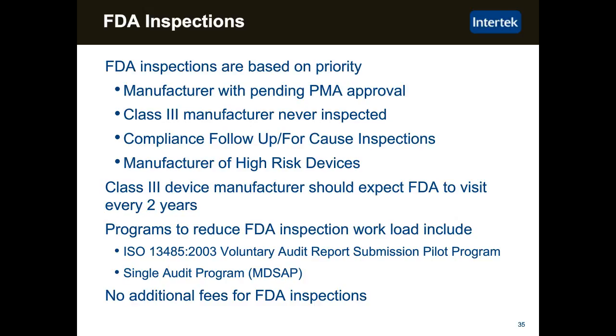There are some programs to reduce FDA inspection workload, and these have been piloted over the past few years. So there is a voluntary audit program where you get audited to ISO 13485. There's also a single audit program, which in 2017-2018 will move from a pilot program into a full-fledged program. In that case, you're audited by a certification body, and that single audit program basically gets you a pass for Brazil, the United States, Canada, Japan, and Australia. There are no additional fees for FDA inspections, but you do pay the annual fee for the site, and that really is intended to cover those inspection costs.